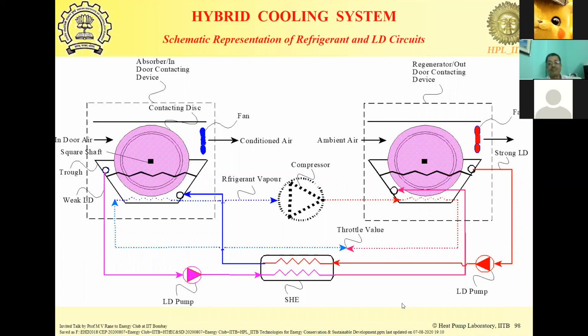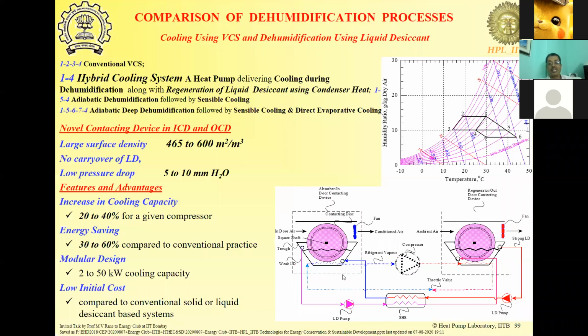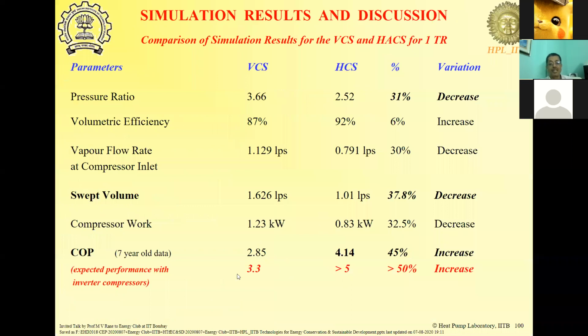And we have achieved COPs as high as 5 with these systems, compared to conventional systems. We had achieved a COP of 4 more than, I think, 15 years ago. And now with better compressors, we can achieve more than 5, while the conventional state-of-the-art 5-star AC is only reaching 3.6 or so today. Okay, then you talked about the dedicated outdoor air systems.